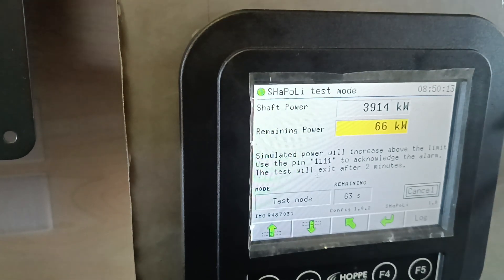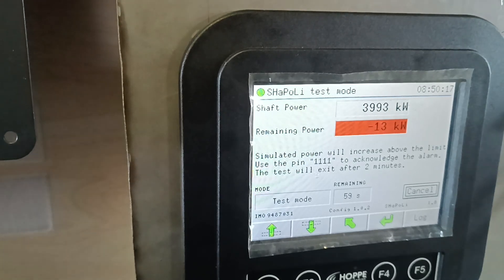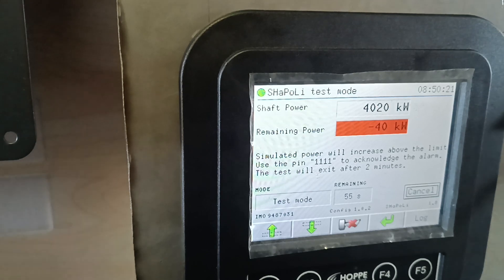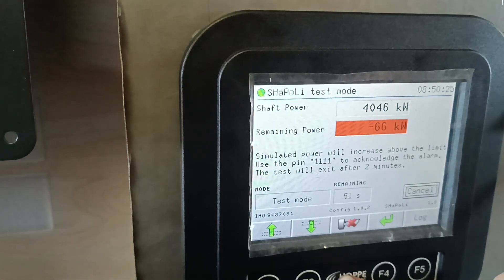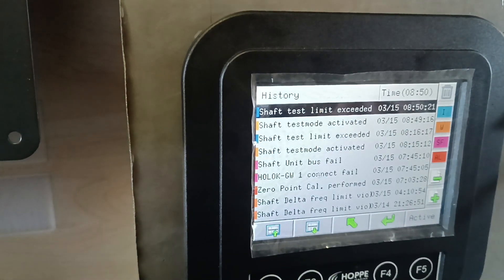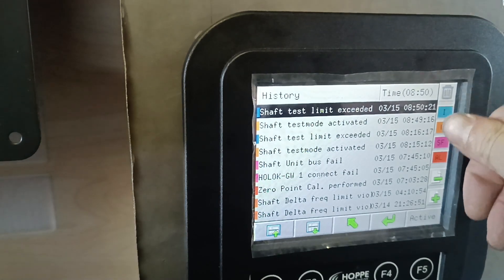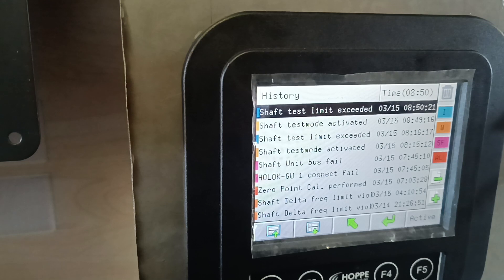Just for alarms. Also, if you enable override mode, I will show you that. Now we're exceeding and we have a full alarm. To get the alarm off, we need to enter PIN level one — that's 1-1-1-1, Enter. PIN acknowledged. And as you see, everything remains in the logs.